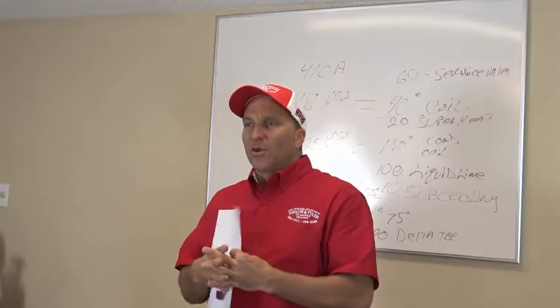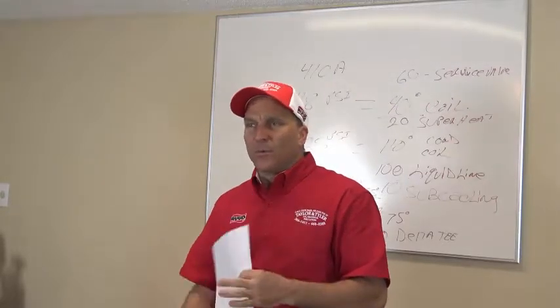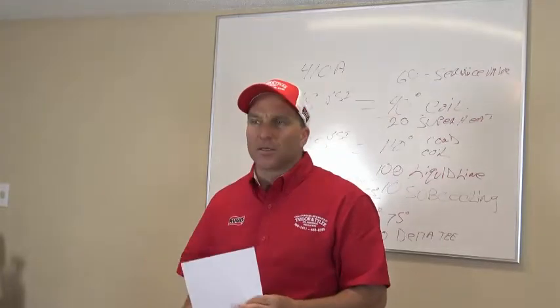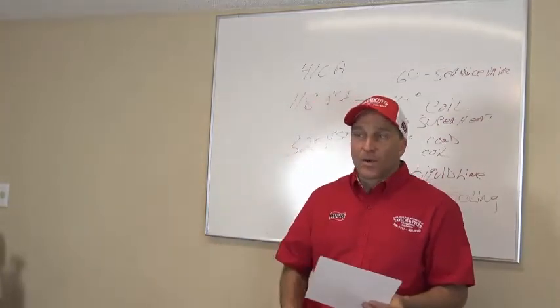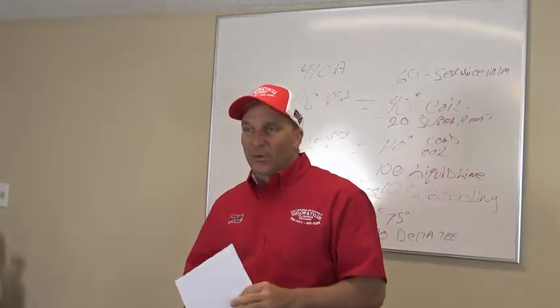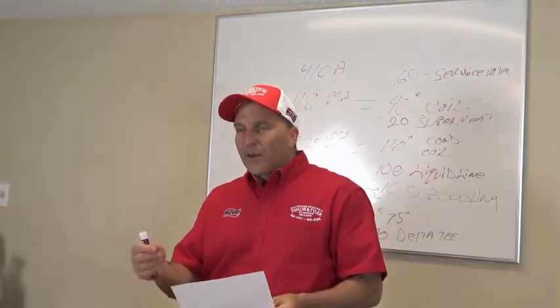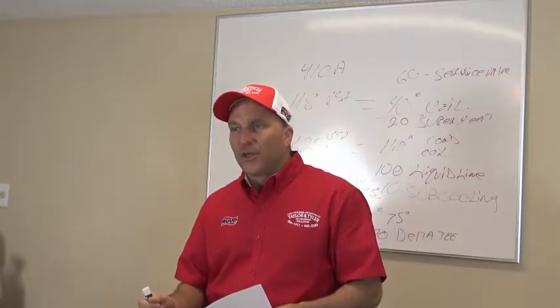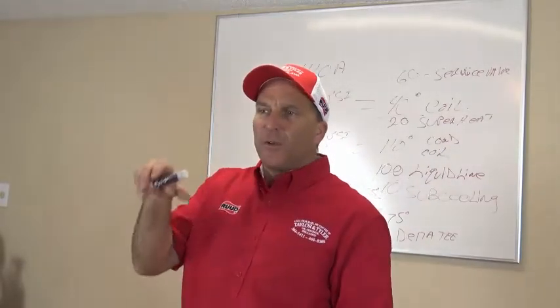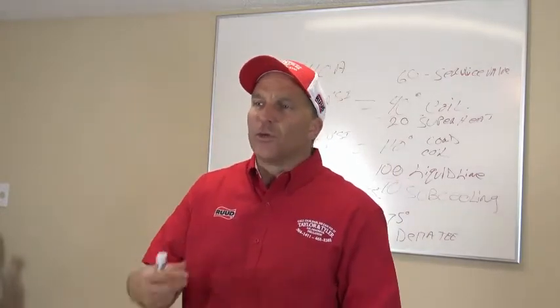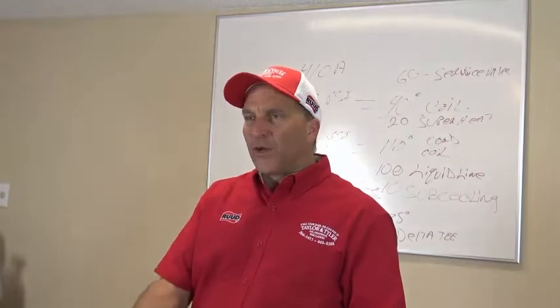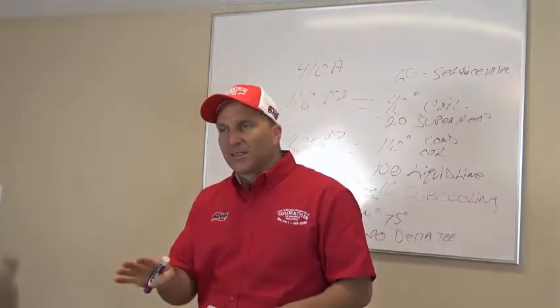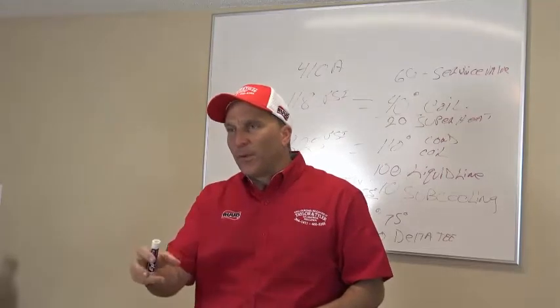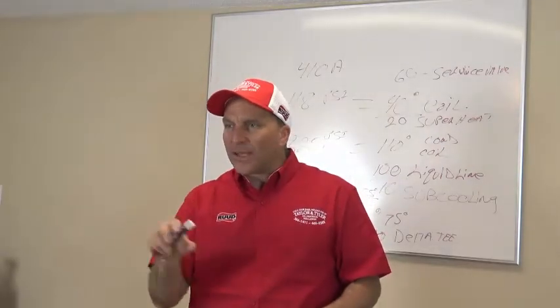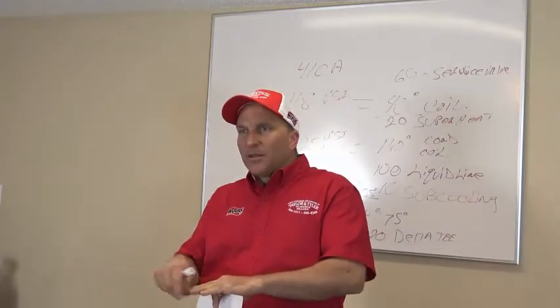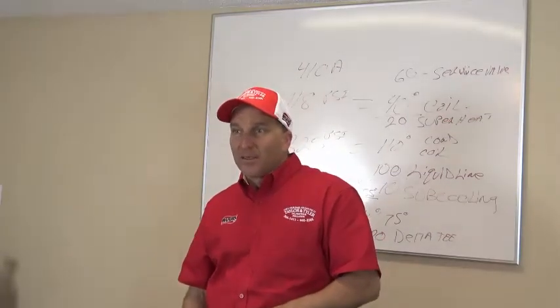Okay? Thermal paste on it, or a wet rag around it, then the paint won't burn, and it won't bubble up, and it won't rust. It may rust in time, but it's not going to rust anytime soon. You caused it. Remember that. Okay? Why do the Schrader pins leak most of the time? Because you didn't put thermal paste on the service valve, or you didn't put a wet rag on the service valve. So when you soldered it, what happens? You heated up the Schrader pin, right? So you don't solder a 7/8 line set without putting thermal paste or a cold rag on that service valve to stop from heating up the service valve. Yeah, make sense, guys? Don't do that.